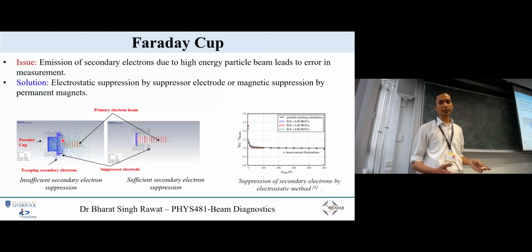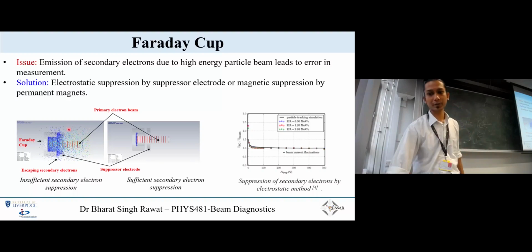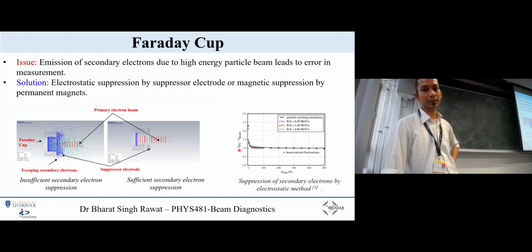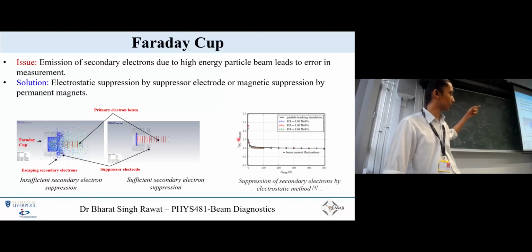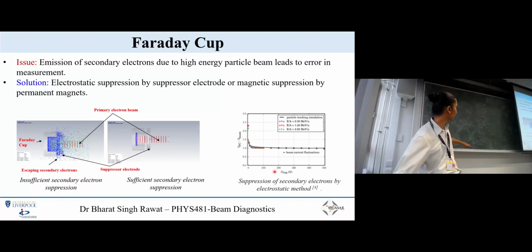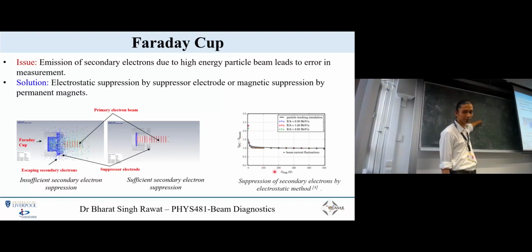And then a typical way of calibrating a Faraday cup is shown in this plot. What you do is you measure the current measured in the Faraday cup, and what is the actual beam current that you expect. You can measure it with another kind of diagnostics, which you already know. And you vary the repeller voltage or the suppressor voltage. So this is the suppressor voltage.